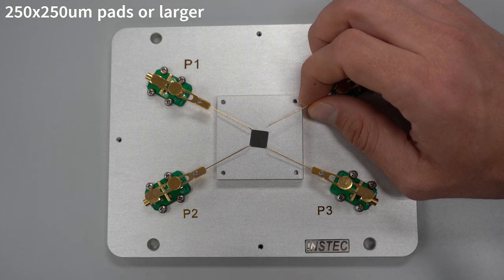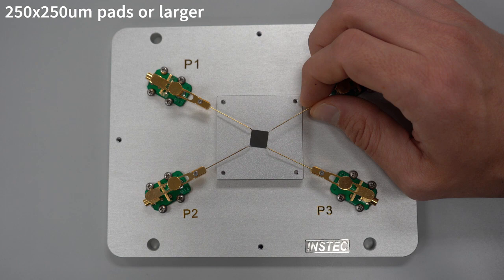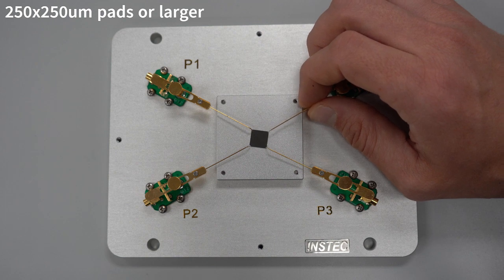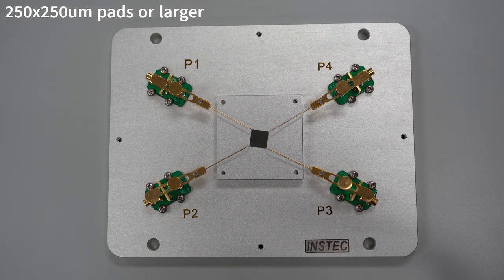The spring-loaded nature of the prober means that we generally use a larger probe tip diameter to reduce pressure on samples. Combined with the manual movement of this sample, it is recommended that you use 250 by 250 micron or larger electrical pad sizes.